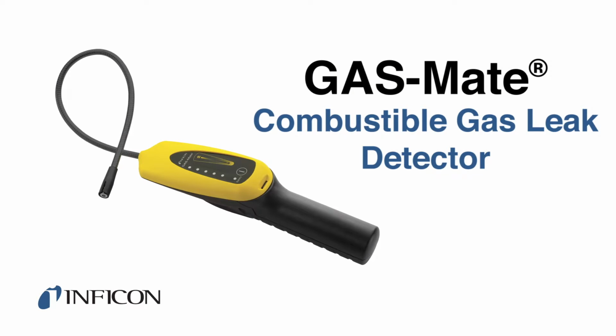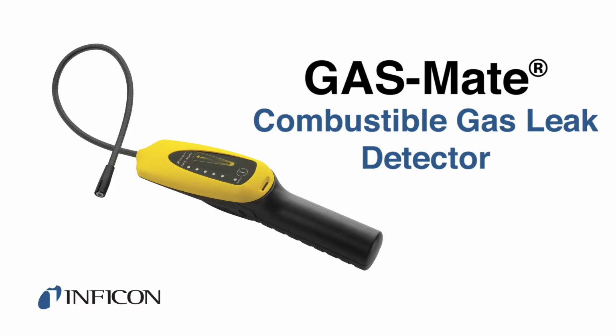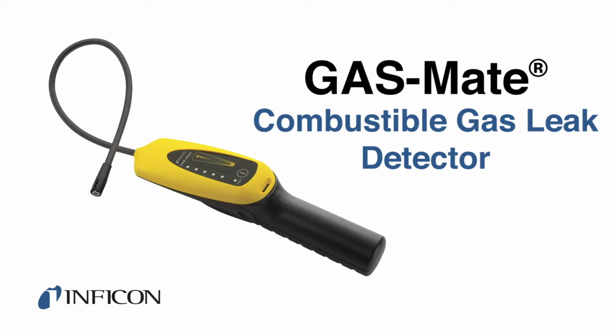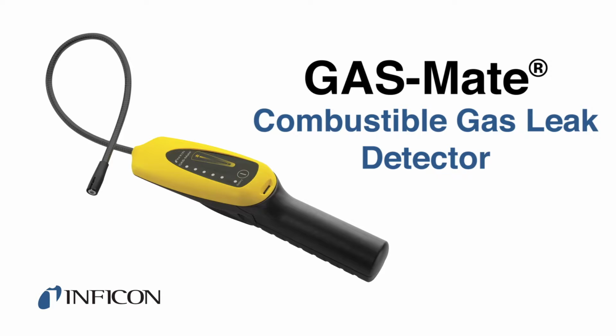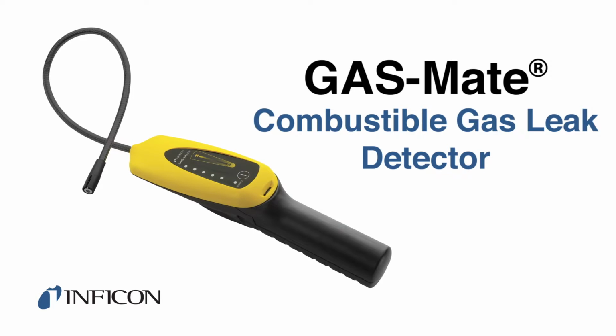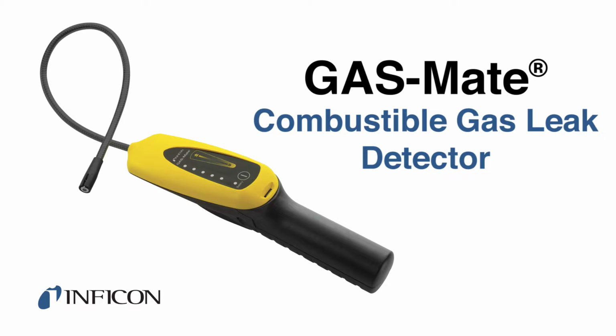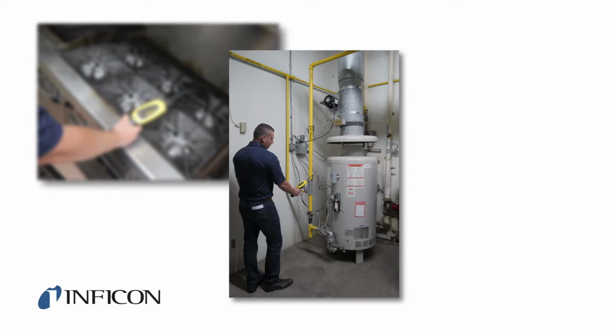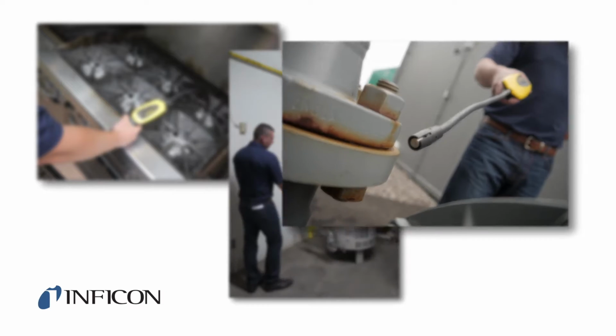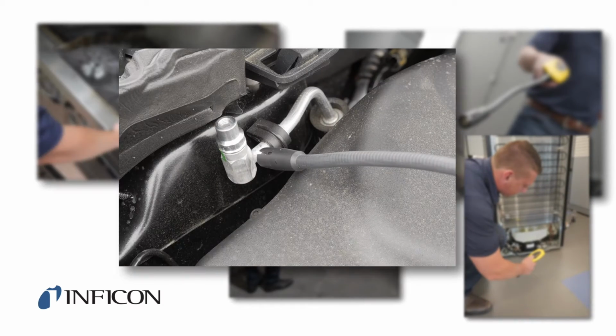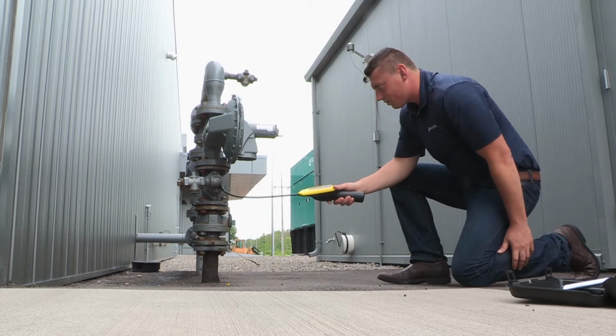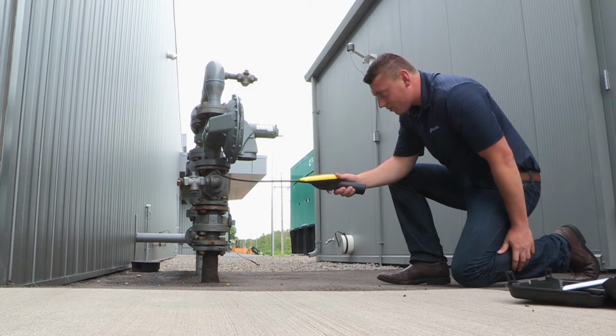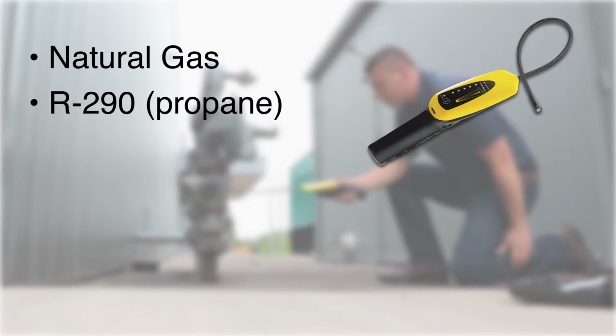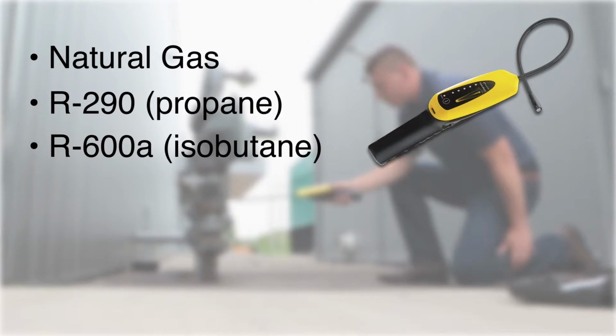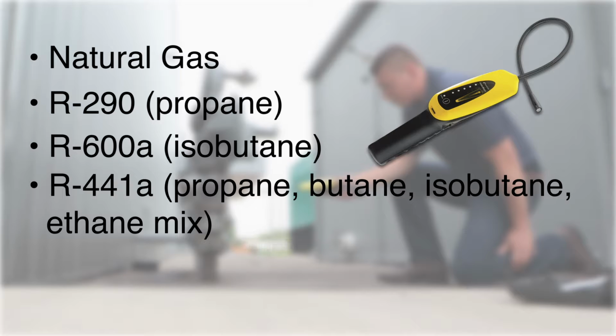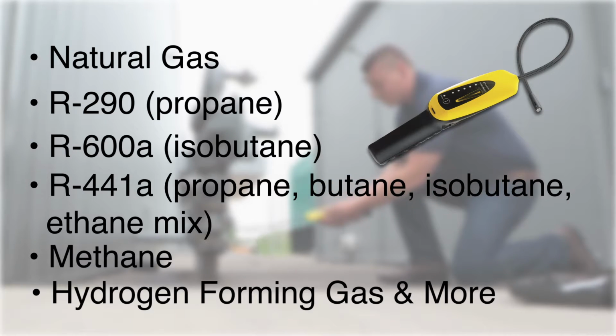Inficon's GasMate is a reliable combustible gas leak detector. This handheld instrument is the ideal tool for locating leaks in heating or refrigeration applications that contain hydrocarbons or flammable refrigerants. These applications can include a gas stove, hot water tank, public utility lines or meters, commercial or residential refrigerators, and automobiles. GasMate detects many combustible gases commonly found on the job site: natural gas, R290, R600A, R441A, methane, hydrogen-forming gas, and more.